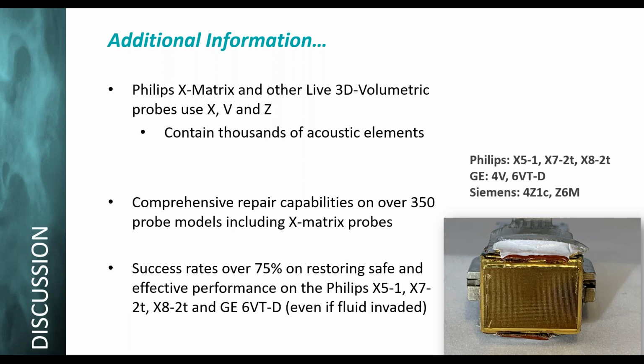So we can fix the connector, we can fix the cable. We manufacture a bunch of different cables, and I think that's one of the questions as well. So we can restore the safe and effective performance on the Philips X's, even if fluid invaded. One of the most common problems with Philips TEE probes is they get breaches in the insertion tubes or the bending rubber, and you get fluid in, and then the probes blow up. We can even fix those.